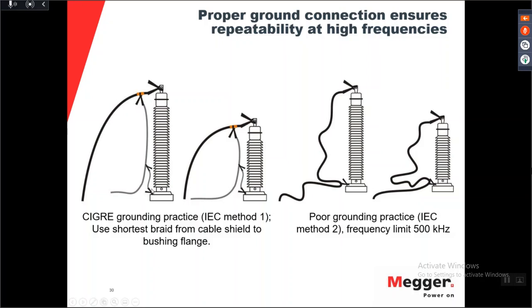Very typical, this part here at the bottom of the bushing is not connected properly, because you can have some paint on your flange of the bushing. So when you connect this, it's connected to the paint and not really connected to the metal of the transformer. So typically you can have a poor connection here. You need to make sure that you're connected through the paint and you have good contact, both here and here.